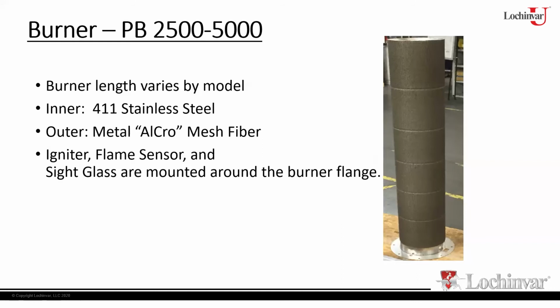So if you have the burner out and you're flushing it out with water, great. Blow it out with air afterwards, dry it off before you put it back in the unit, okay? So just do it that way if you're going to use it. But again, the way that we showed in the videos is just using air. That would be the way that would be recommended. So just take your time with it. Again, as you have it out, make sure there's no physical damage to the burner, no rips, no tears, anything of that nature. If there is physical damage, then it's got to be replaced at that point.